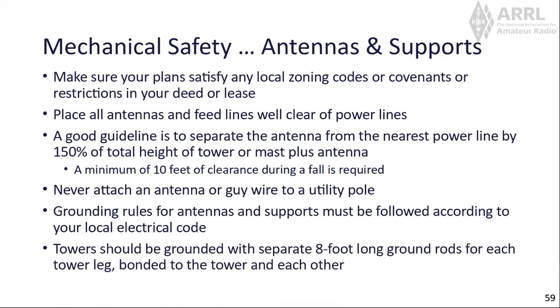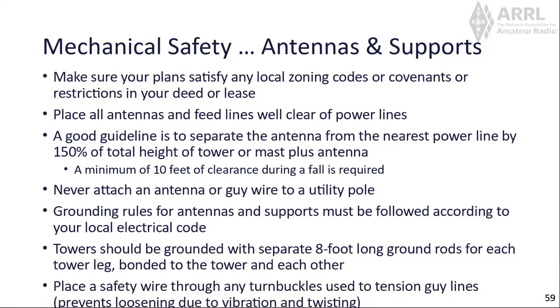Towers should be grounded with separate 8-foot long ground rods for each tower leg, bonded to the tower and each other. And before you dig, call the people that come out and locate the utilities. Because if you drive a ground rod through a gas line or water line or an underground electrical line, you will pay. Place a safety wire through any turnbuckles used to tension guy lines. It prevents loosening due to vibration and twisting.